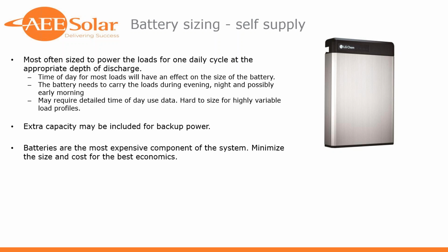And of course, if the customer also wants backup power, you may need to have a little extra capacity in your battery bank to handle that backup power, even if they don't need it necessarily for the self-supply. And people do put a value on being able to use their solar system and their battery bank when the utility power goes down.